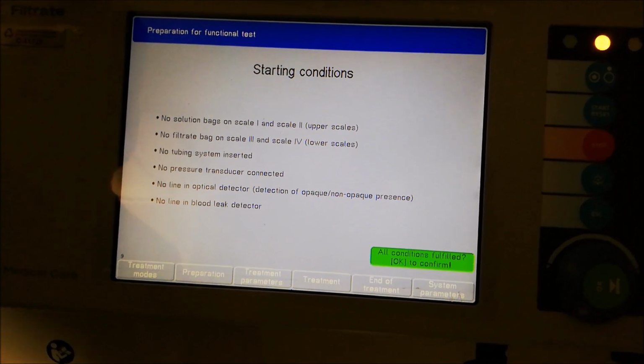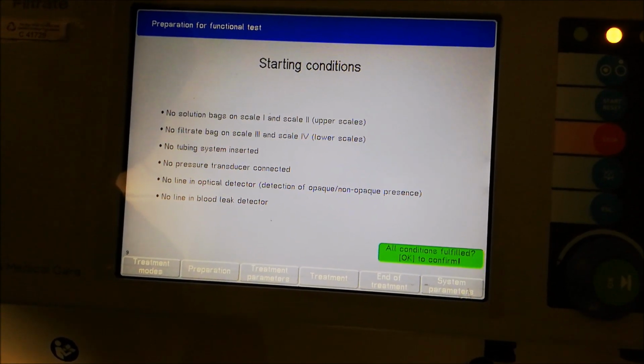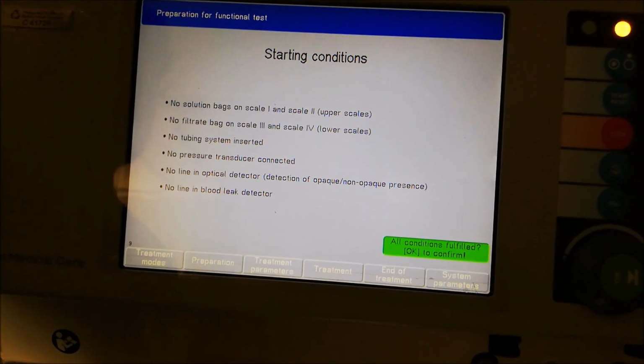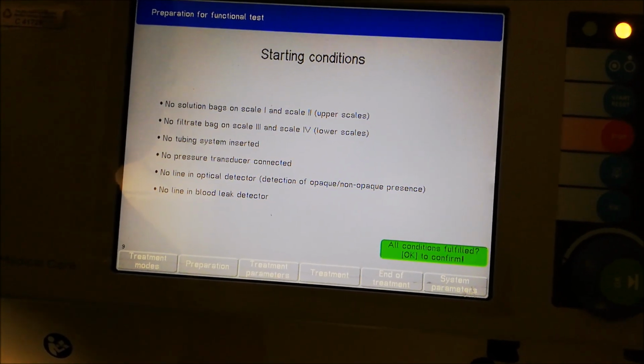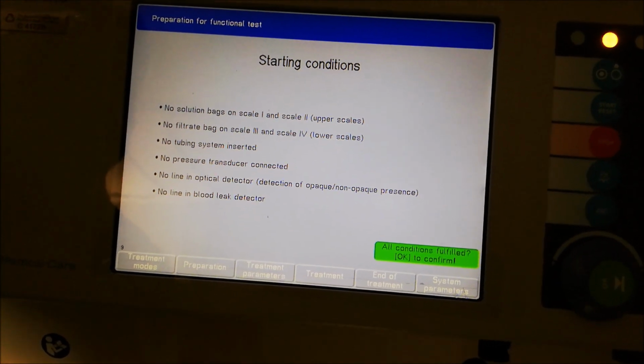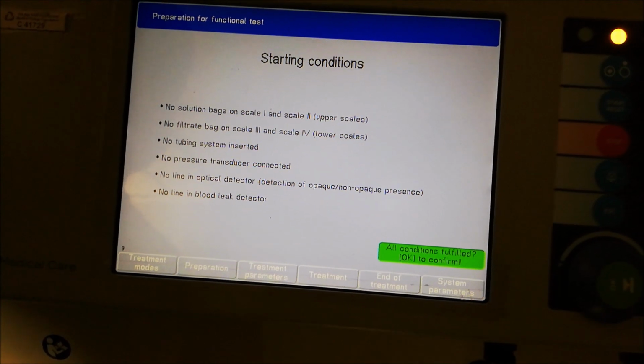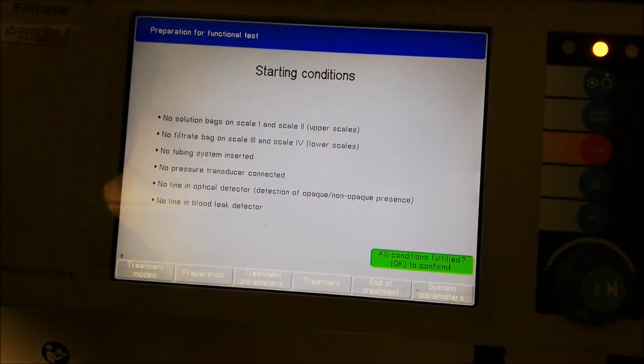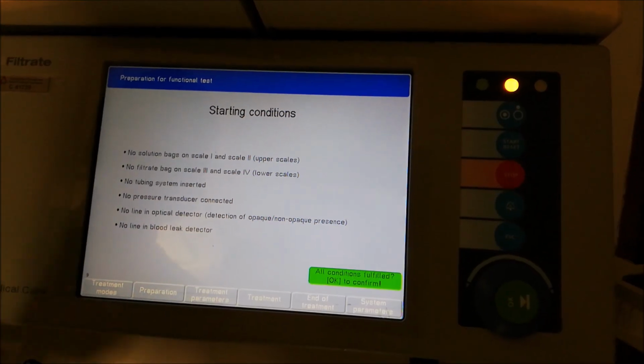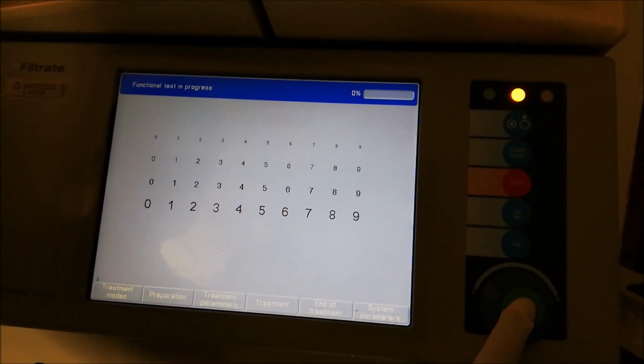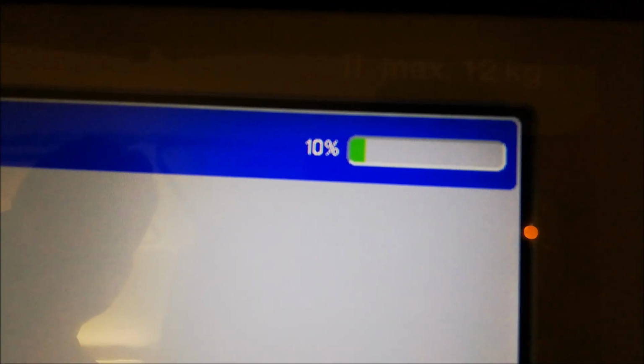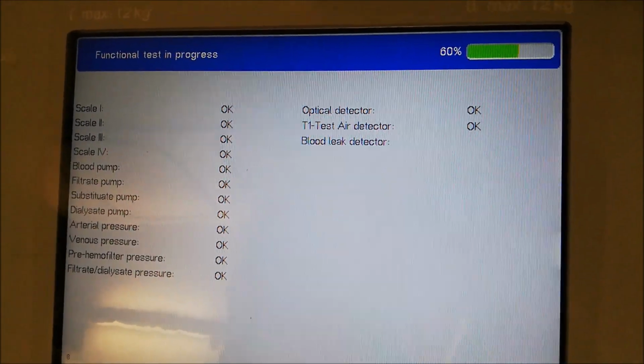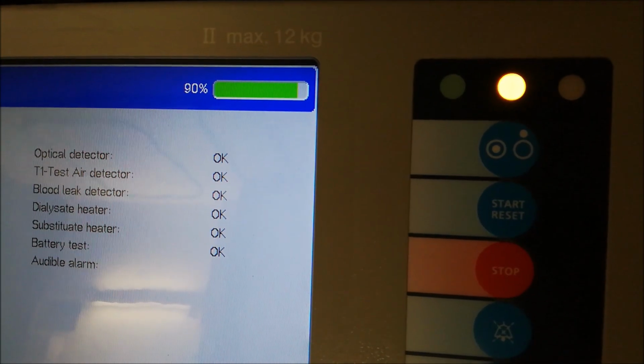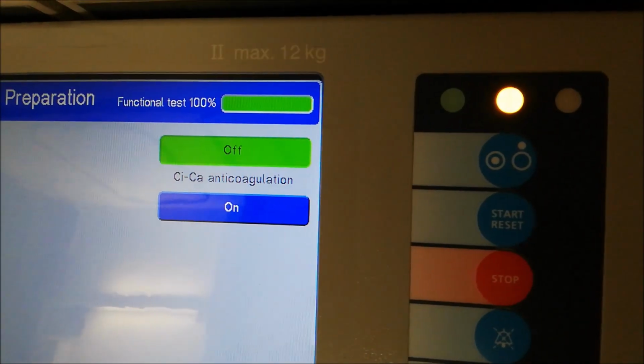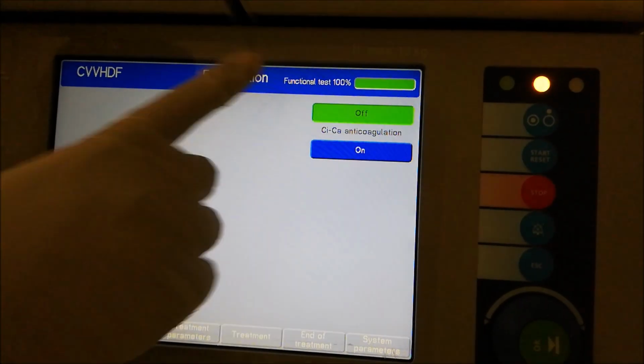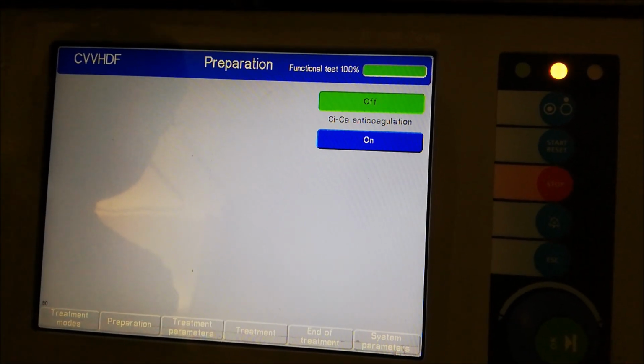Let's see starting conditions, which are no solution bags on scale 1 and scale 2, no filtrate bag on scale 3 and scale 4, no tubing system inserted, no pressure transducer connected, no line in optical detector, and no line in blood leak detector. As all conditions are fulfilled, press OK to confirm. Machine has passed functional test 100%, which means our machines are 100% working properly.